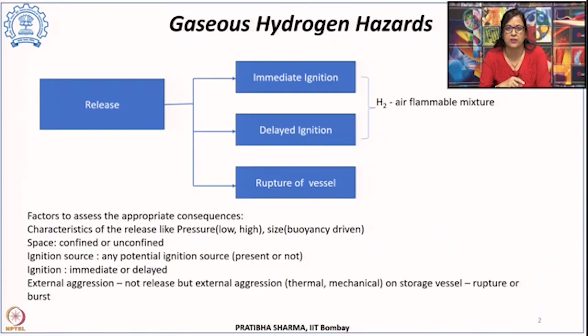Another important parameter that will describe the consequence is whether that release was in a confined space or in an unconfined space, and they will have different challenges. Whether there was an ignition source present or not, that again will lead to different hazards. If there was an ignition source present, was the ignition immediate or was it delayed? Other than the ignition source, there could be a rupture of the vessel aggravated by some external aggression, such as a nearby fire which has resulted in a domino effect and rupture of the vessel, or a mechanical impact that has resulted in the rupture or burst of the vessel. So, all these parameters will decide the consequences of the gaseous hydrogen release.